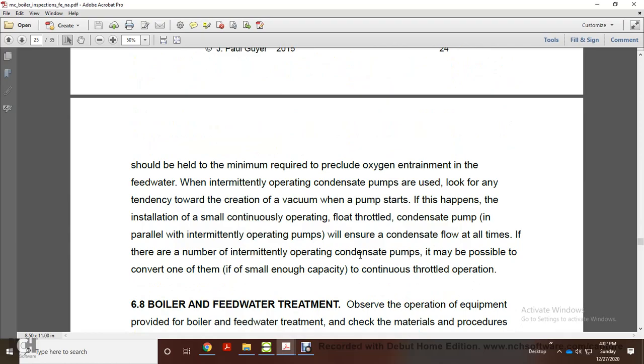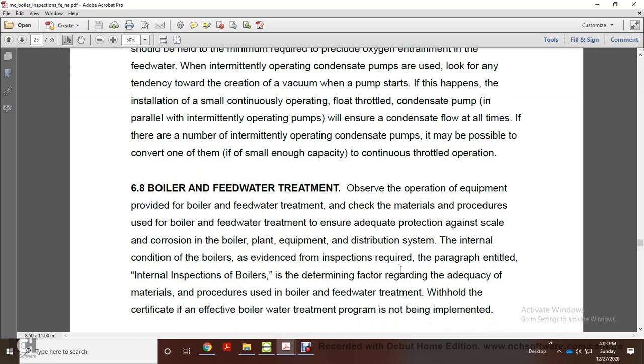Where intermittent operation condensate pumps are used, look at the tendency toward creation of a vacuum when the pump starts. This can be addressed by installing a small continuously operating, float throttled condensate pump in parallel with the intermittently operating pumps, which will ensure the condensate flow. Of the intermittently operating condensate pumps, it may be possible to convert one of them, if small enough, to continuous throttled operation.